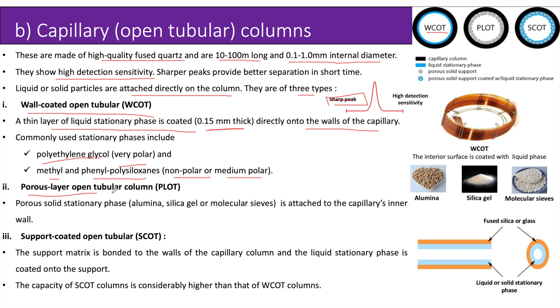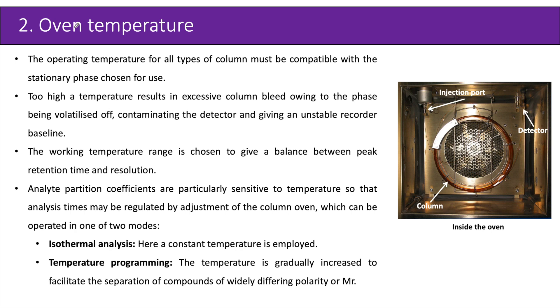Next is the porous layer open tubular column (PLOT), where a porous solid stationary phase such as alumina, silica gel, or molecular sieves is attached to the capillary's inner wall. Then there is the support coated open tubular (SCOT), where a support matrix is bonded to the walls of the capillary column and the liquid stationary phase is coated onto the support. The capacity of SCOT columns is considerably higher than wall coated open tubular columns.